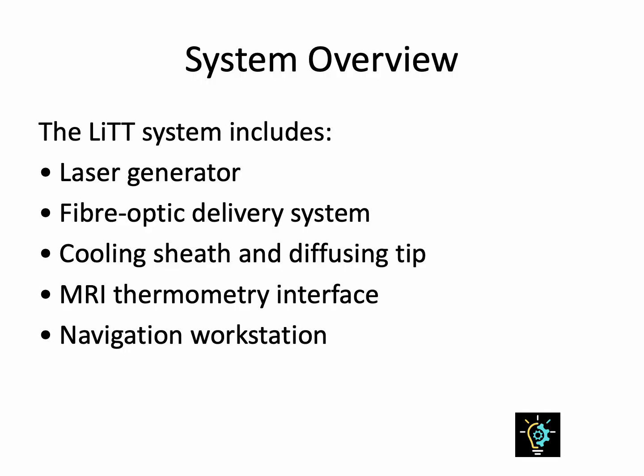A complete LiTT system is a coordinated network of hardware and software. The laser console generates controlled light pulses, typically near infrared at 1064 nanometers. The fiber optic cable transmits this energy into tissue through a cooling sheath that maintains probe integrity. The MRI system provides thermal imaging feedback to the workstation, which displays real-time thermal maps for the surgeon. The integration of all these components ensures precision and safety. Engineers must synchronize laser output, imaging refresh rates, and system communication protocols to maintain thermal control and avoid collateral damage.